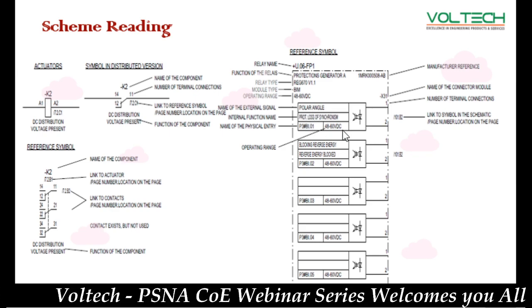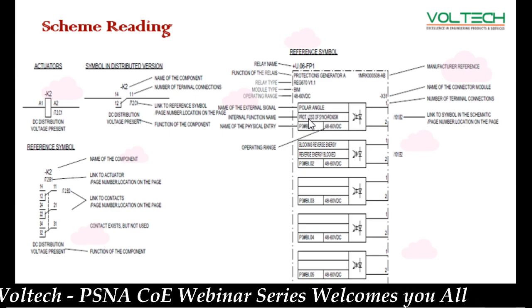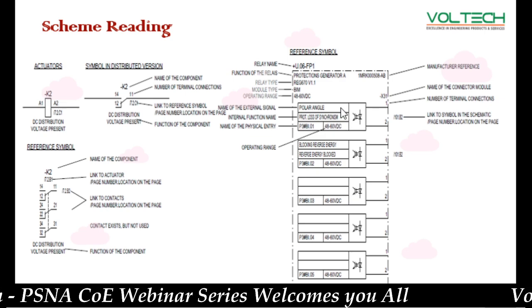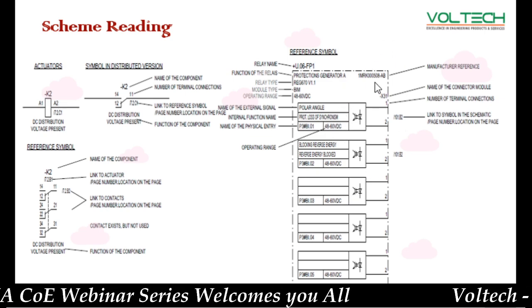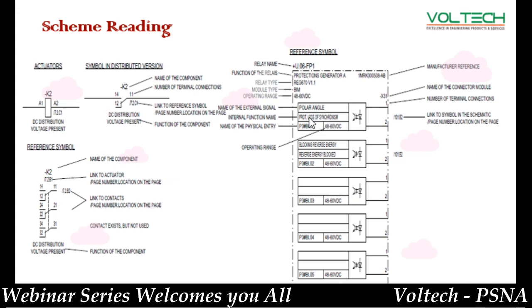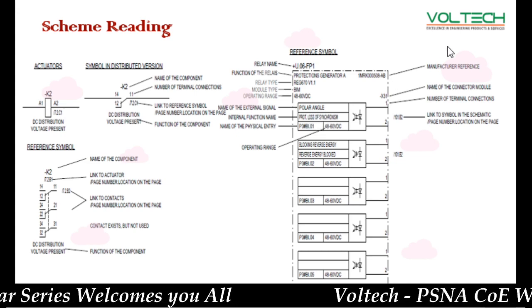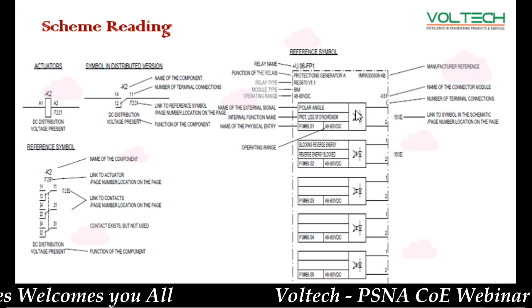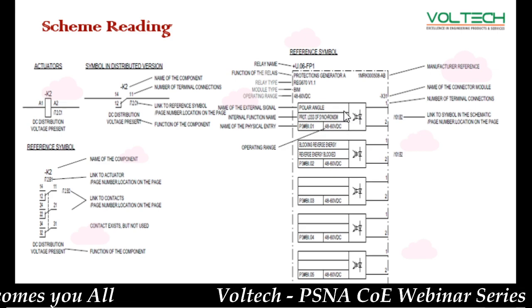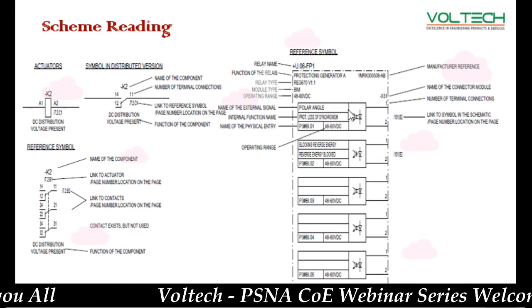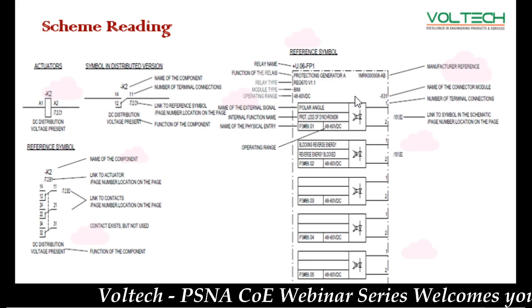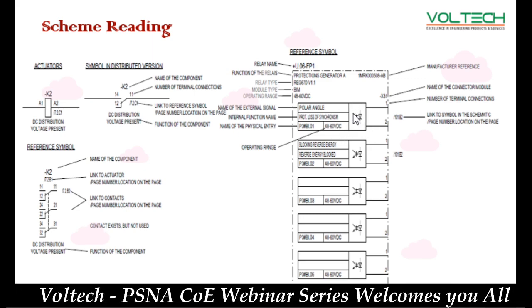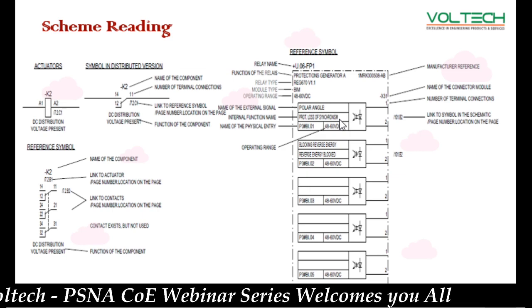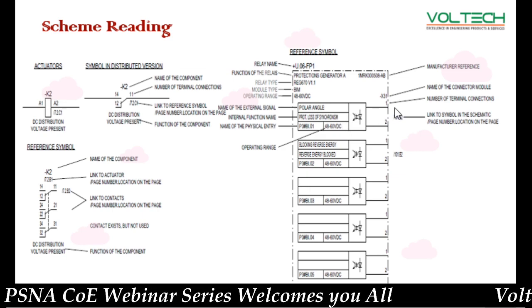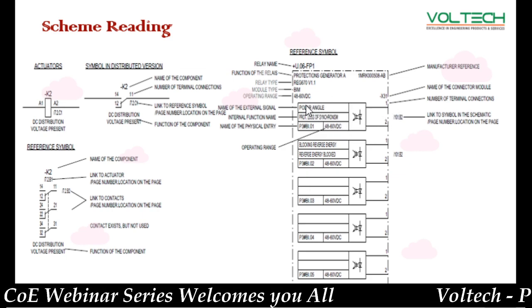It's a name used for the loss of synchronization. For the generator, we are using the synchronization function. When synchronization is lost, the input is given from the field to the relay in the form of DC. Whenever you get the DC voltage, it becomes 1, showing the polar angle, meaning the loss of synchronization has happened. So we have to shut down the generator.